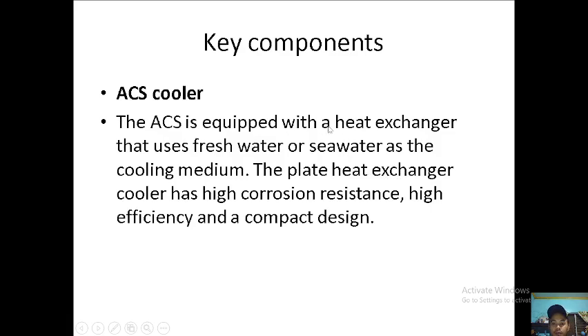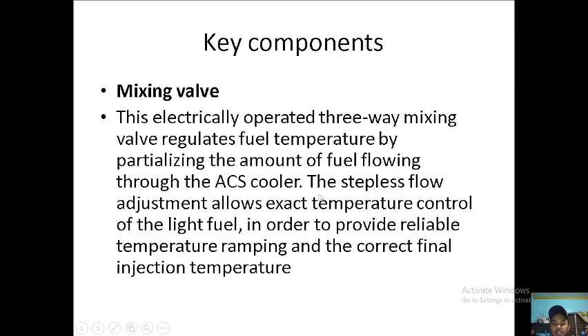It is equipped with a heat exchanger that uses fresh water or seawater as the cooling medium, with high corrosion resistance, high efficiency, and compact design. The mixing valve is electrically operated and regulates fuel temperature by partializing the amount of fuel flowing through the ACS cooler. The stepless flow adjustment allows exact temperature control of the light fuel in order to provide reliable temperature ramping and the correct final injection temperature and viscosity.